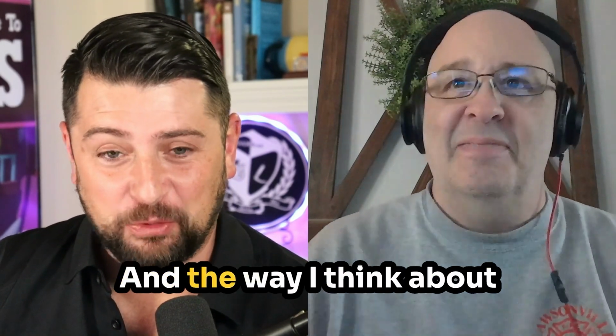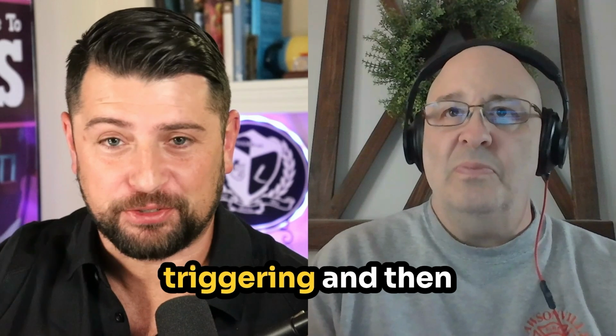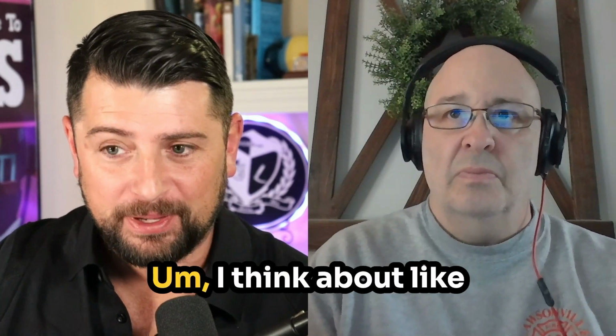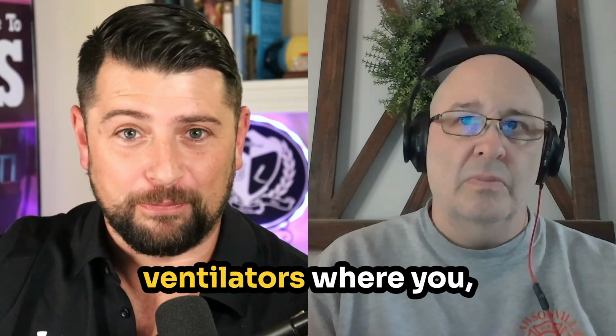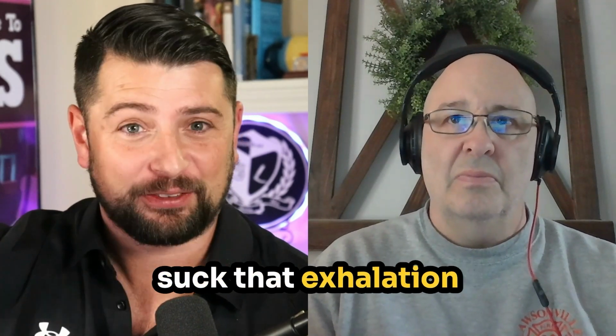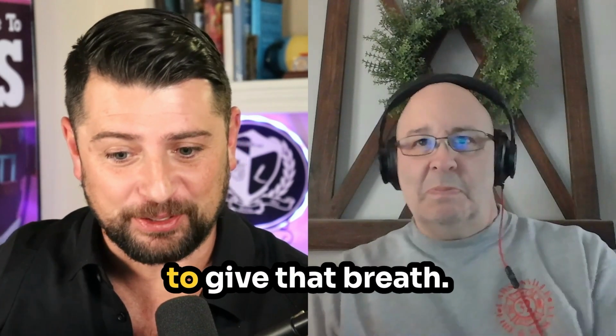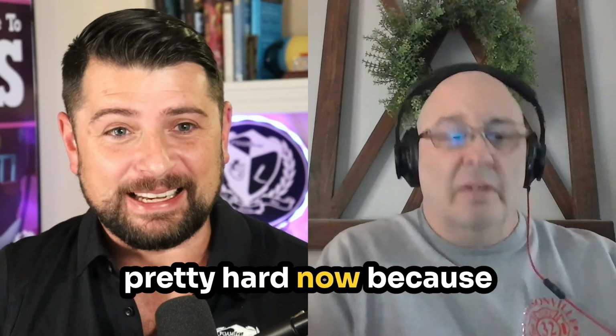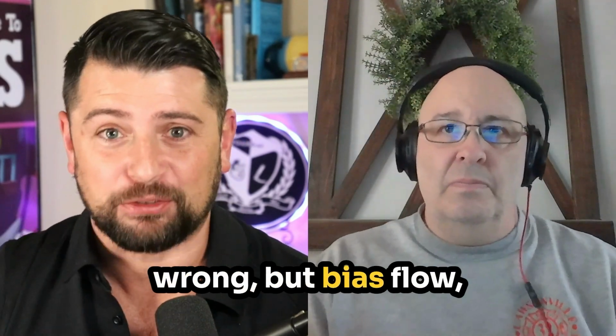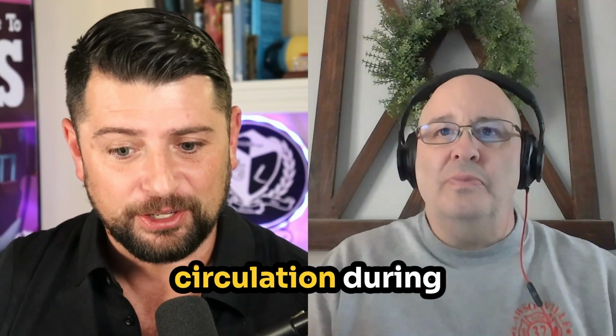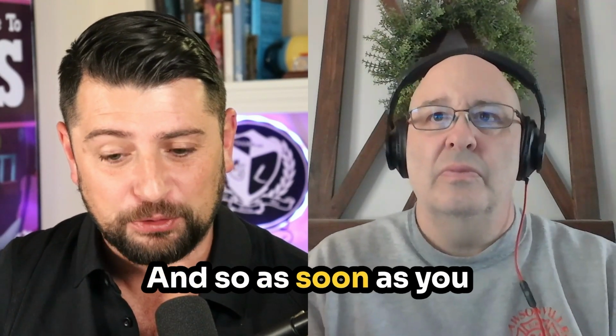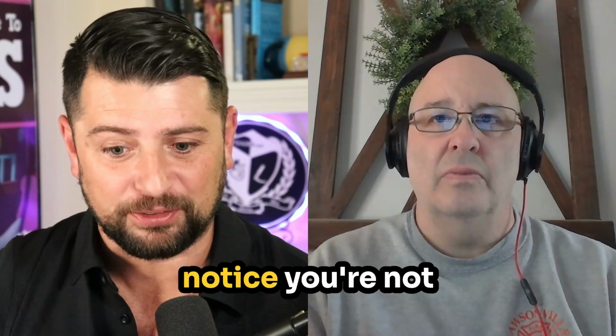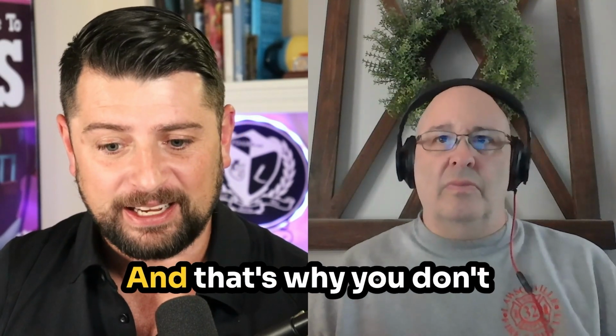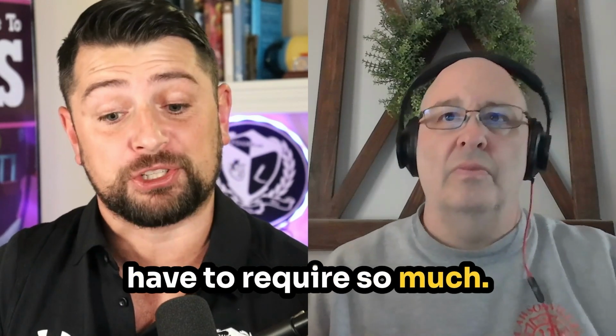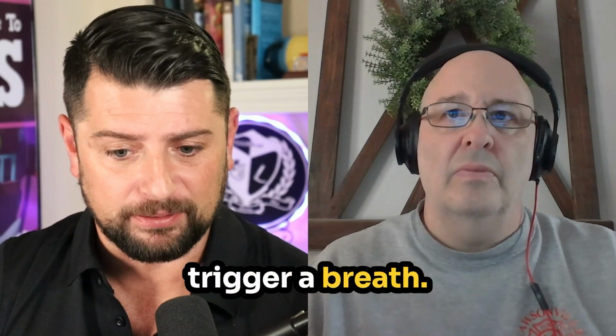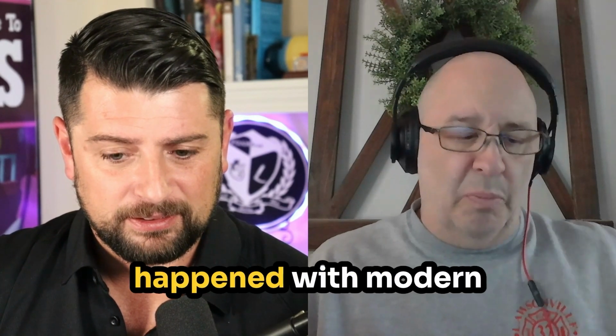No, that's great. And the way I think about the triggering is, there's pressure triggering and then there's flow triggering. I think about the old ventilators where you'd suck in and you'd suck that exhalation valve closed when you went to take a breath, and it would trigger to give that breath. I mean, you had to work pretty hard. Now because of, and correct me if I'm wrong, bias flow, you have this constant circulation during the exhalation phase. And so as soon as you switch to inspiration, it's going to instantly notice you're not getting as much back as it's sending out. And that's why you don't have to require so much flow in before you trigger a breath. Is that correct?